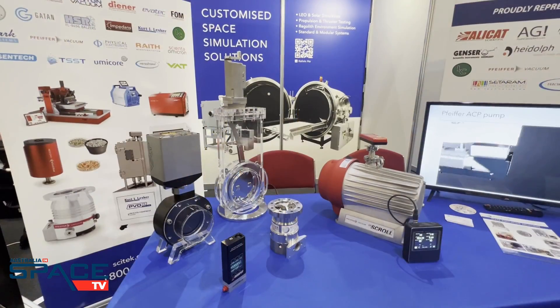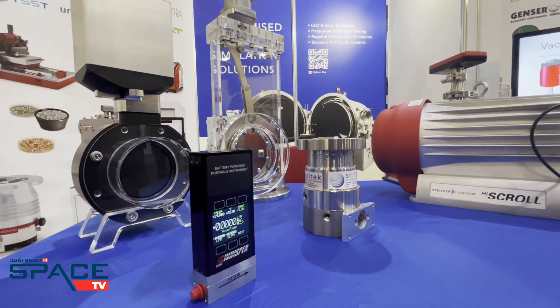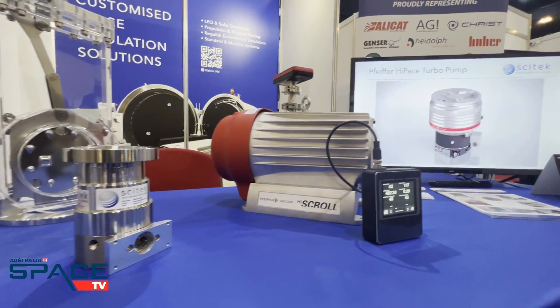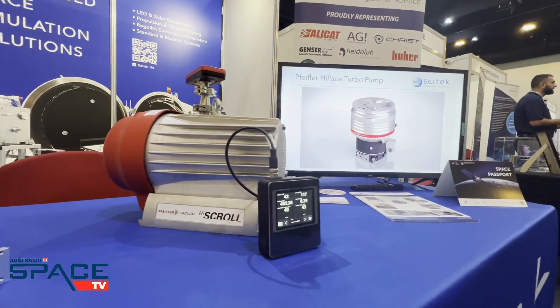Is this some models that you've got here in terms of the vacuum platforms that you have? For sure. So what you see here is some equipment used in what we call a thermal vacuum chamber or a vacuum chamber. We have some valves to isolate the chamber, some mass flow meters to inject gas for propulsion testing, and the turbo pumps to do your actual low earth orbit simulation down to 500 kilometres above sea level.